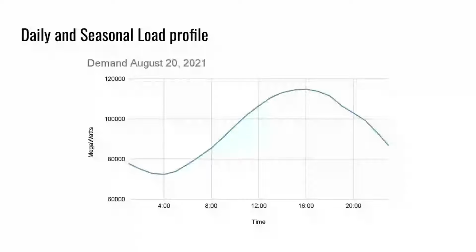So what will happen on this day, the highest 15 minutes that occurred during that day is the power charge that the co-op would pay for that day. When Dairyland Power calculates that power charge, they'll do this on the highest 9 or 10 days out of the year, and then somehow work those numbers together to determine what the final power charge that Scenic Rivers pays is.